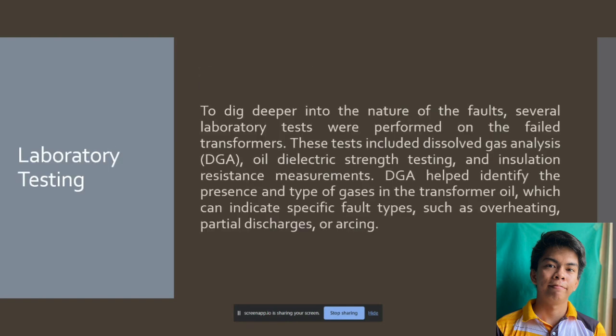Analysis of the issues. So first is the laboratory testing. To dig deeper into the nature of the faults, several laboratory tests were performed on the failed transformers. These tests included dissolved gas analysis or DGA, oil dielectric strength testing, and insulation resistance measurement. DGA helped identify the presence and type of gases in the transformer oil, which can indicate specific fault types such as overheating, partial discharging, and arcing.